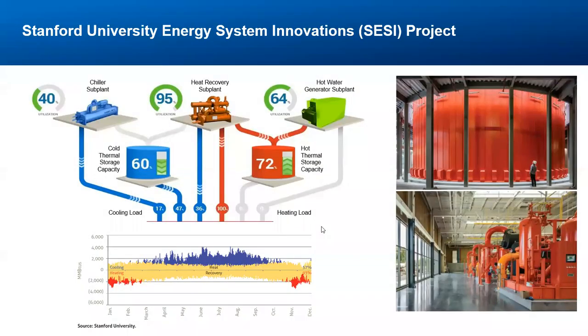This one doesn't have a ton of equipment, but it is a lot of large equipment. What makes it complex is the storage dynamics and the utility rate and real-time pricing dynamics of the system. Key features include three 2,500-ton heat pump heat recovery chillers, four centrifugal chillers, and a hot water generator for cases where they need natural gas to complement the heat recovery plant to meet the campus's heating needs.